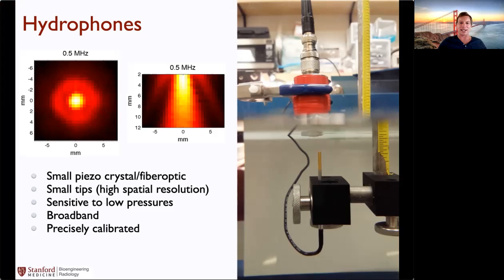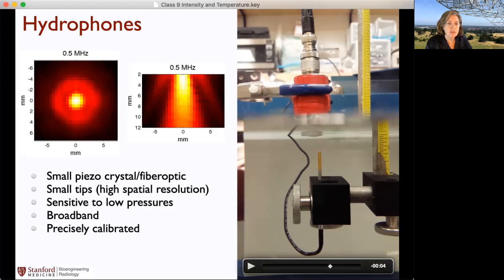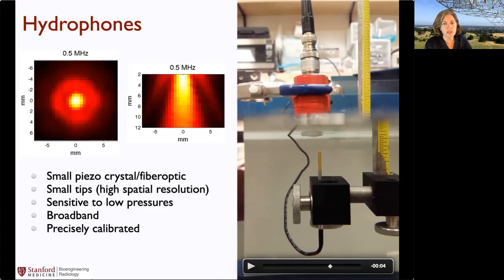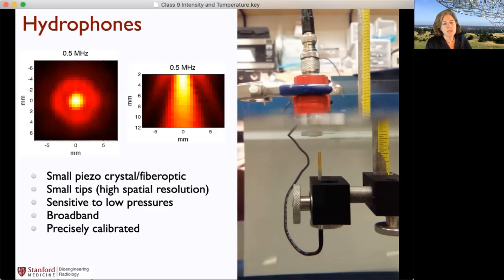So are these optical measurements that are made? I forget how the hydrophone actually works. Well, it depends. This is usually a small piezoelectric crystal, so it's just a transducer picking it up, just like all the others we talked about. Typically very small tips, so you can get high spatial resolution. Typically, they're very, very sensitive to low pressures. So that's something we'll talk about in just a minute on what that means.